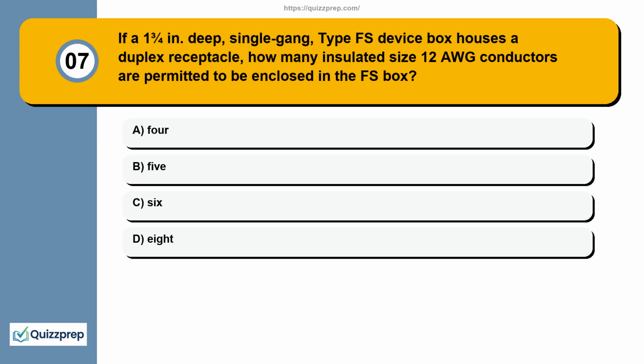Question 7. If a 1 3/4 inch deep, single gang, type FS device box houses a duplex receptacle, how many insulated size 12 AWG conductors are permitted to be enclosed in the FS box? 4, 5, 6, 8.